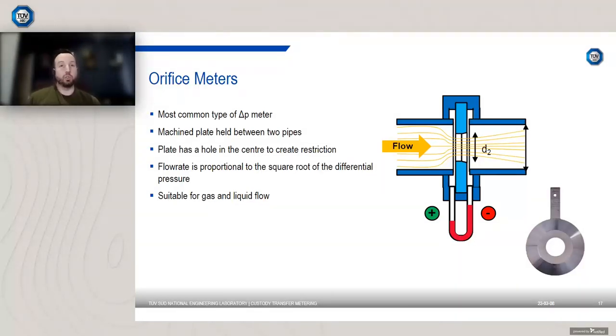So you measure the differential pressure, and along with the fluid density, the area, and the discharge coefficient, which is the ratio of the actual flow rate to the ideal value through an orifice and accounts for frictional effects, you can determine the mass flow rate through the orifice. They're quite a simple design, and they're suitable for both gas and liquid flow. So they're quite versatile.